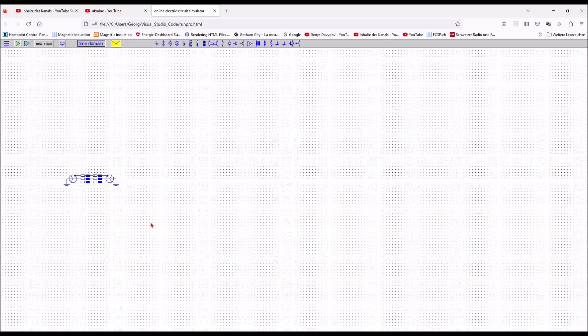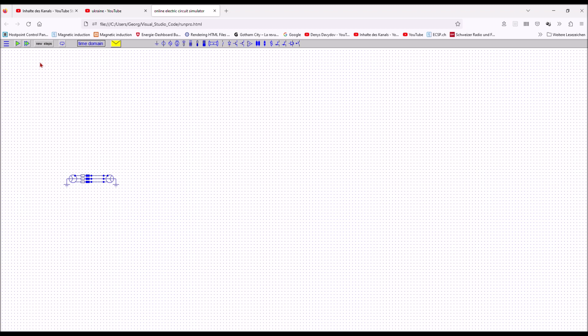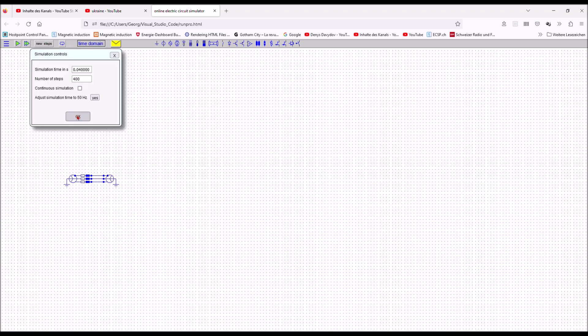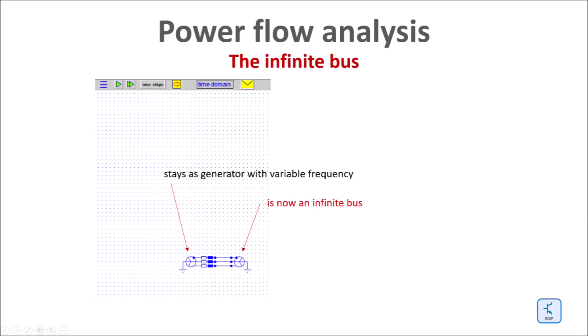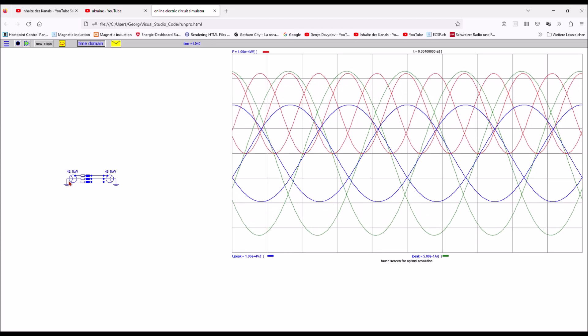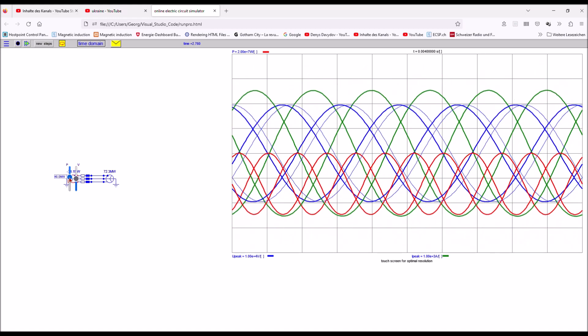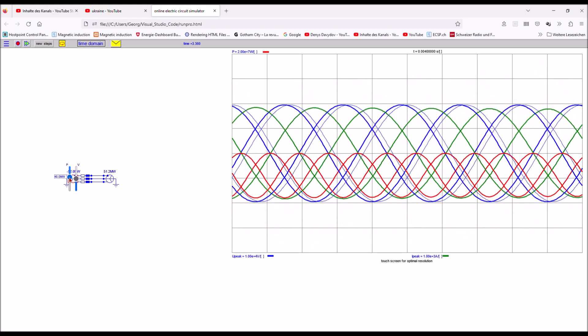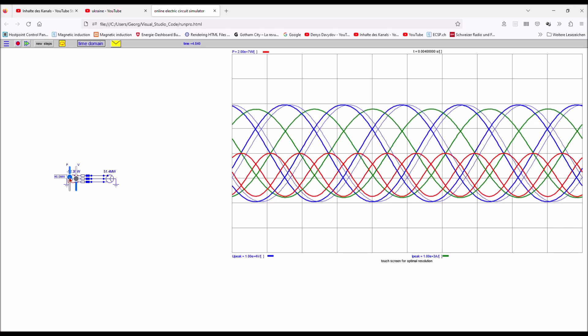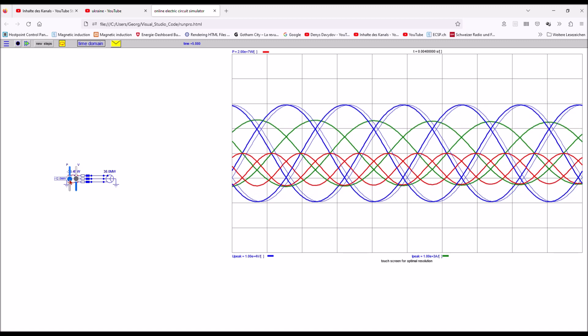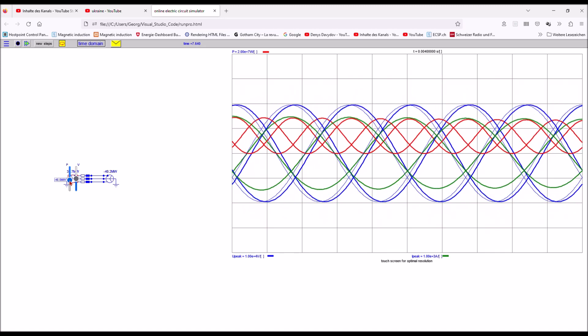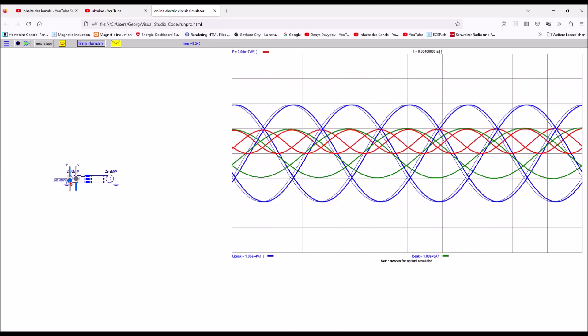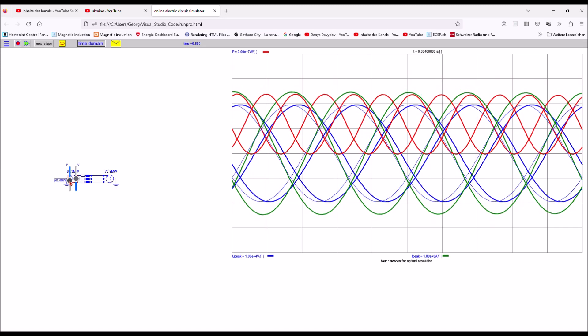In a power flow analysis I would normally set one of the generators as a so-called infinite bus. This is a pure stiff voltage source without any impedance and with fixed frequency. This infinite bus would swallow all real power or reactive power imbalance and so the rest of the system can be analyzed and optimized properly. The generator with variable frequency to the left can now act either as a generator or as a motor, but the frequency in this case would always stay stable at 50 or 60 hertz.